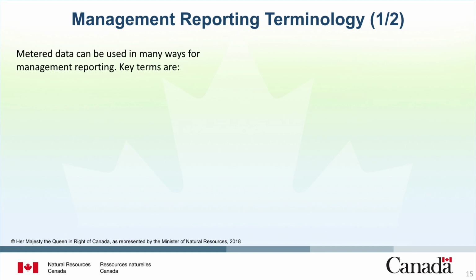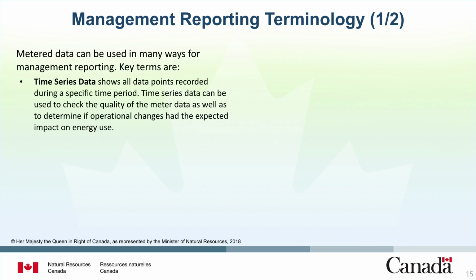Meter data can be used in many ways for management reporting. Some key terms for management reporting are time series data, total energy or water consumption data, annual energy consumption data, and energy or water use intensity. Each of these terms is described in turn. Time series data shows all data points recorded during a specific time period. Time series data can be used to check the quality of the metered data as well as to determine if operational changes had the expected impact on energy use.